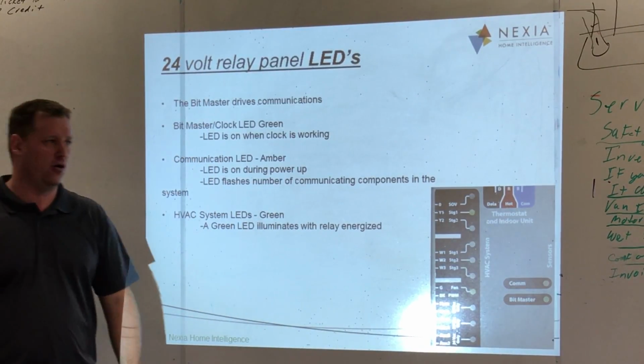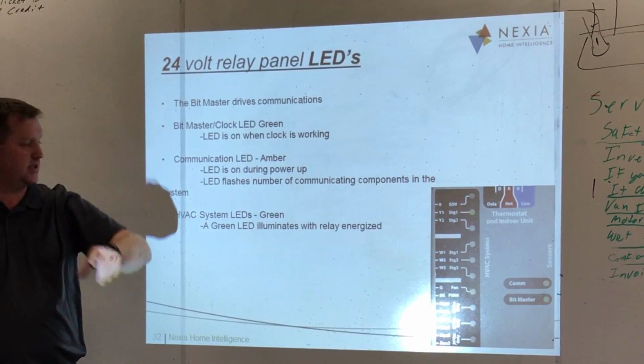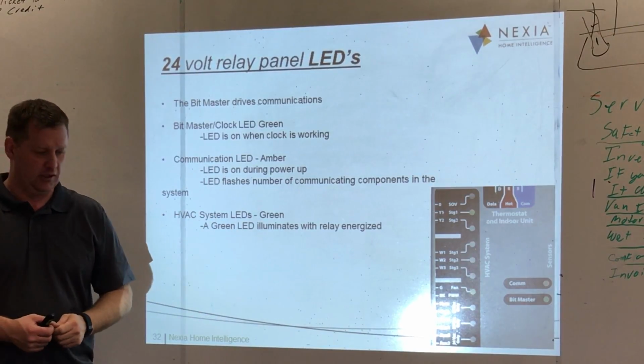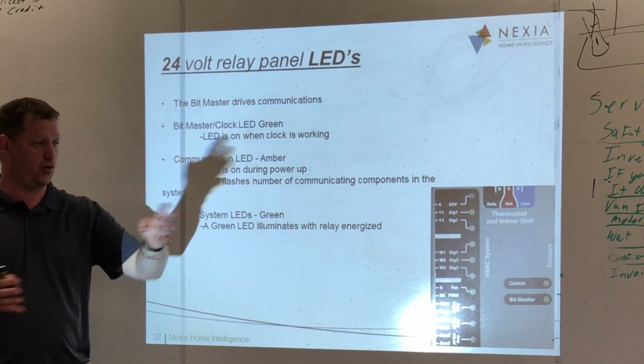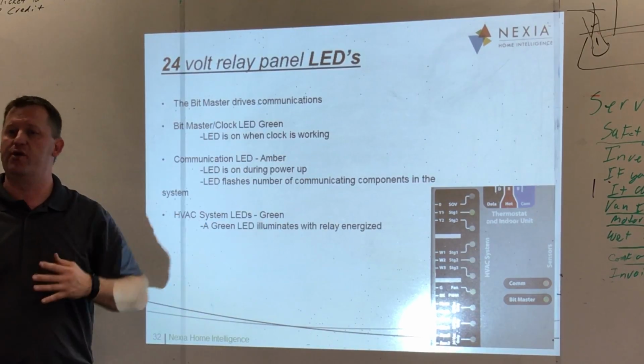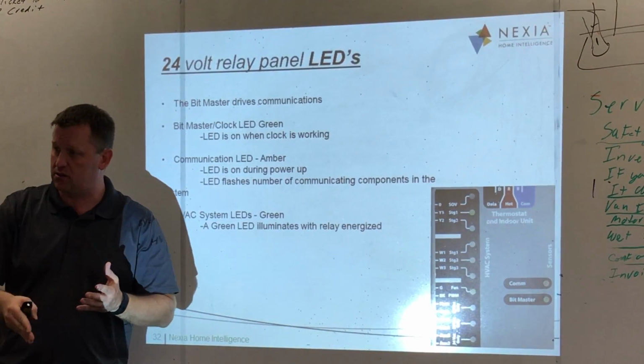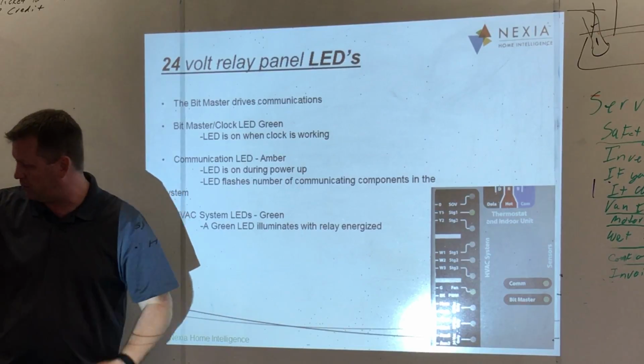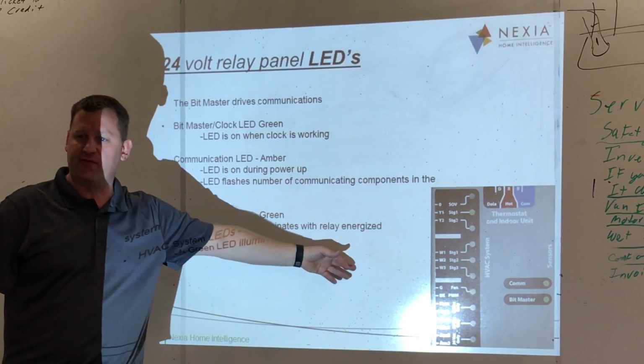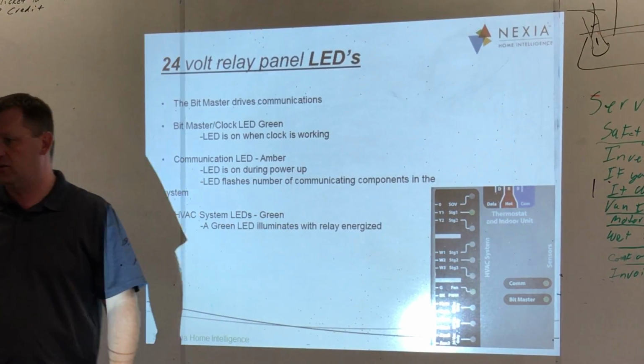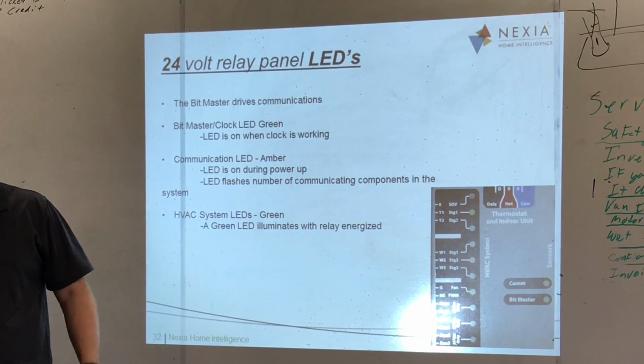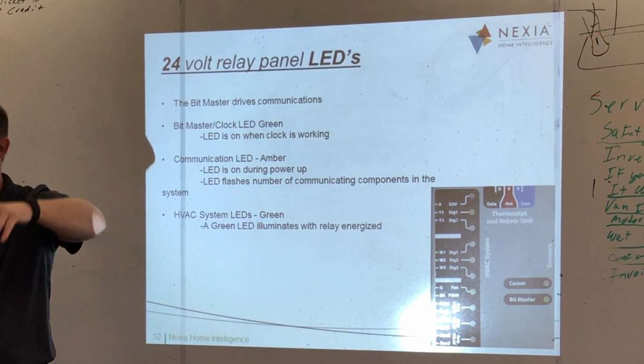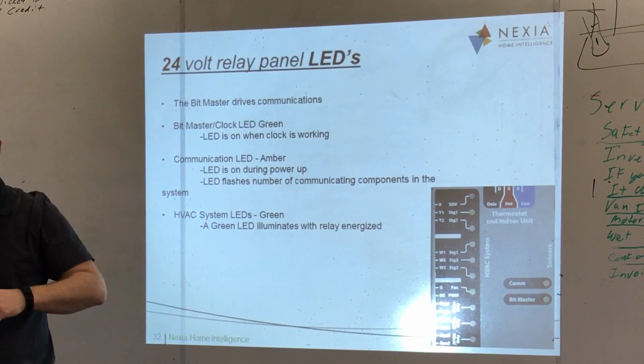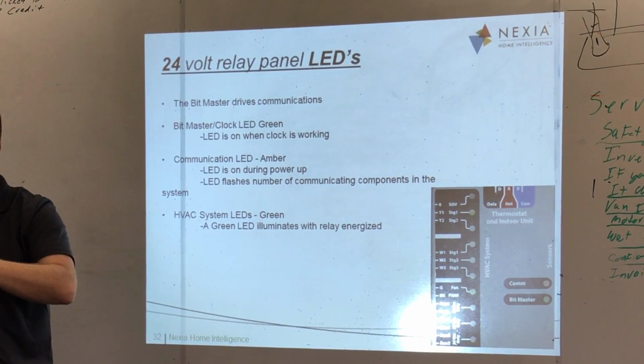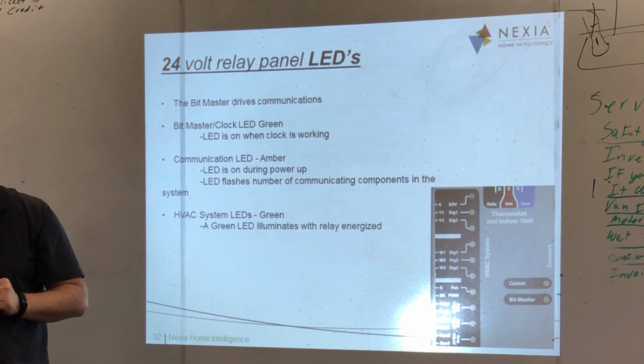So now you can go, okay, I've got this, I've got this, I've got this on the data terminal, the D wires, that should create this many flashes. Okay, I'm missing something, then you can go into that summary table, see what's talking and what isn't, and go, oh crap, I should have 7 flashes because I've got a communicating clean effects. And you go to the summary table and see, okay, indoor unit, outdoor unit, relay panel, 940, 940. Where's my clean effects? So you can see that info.